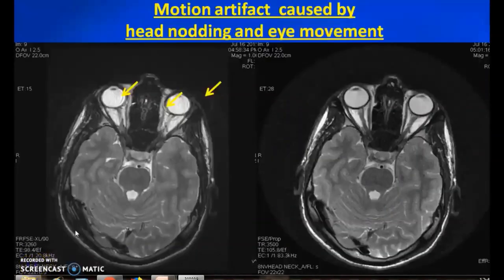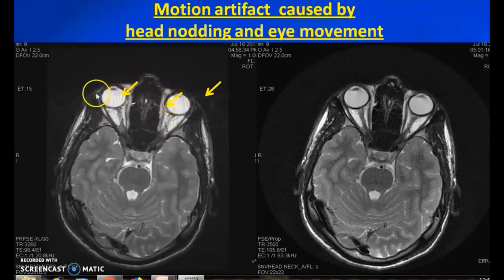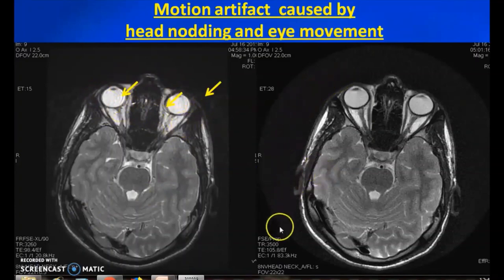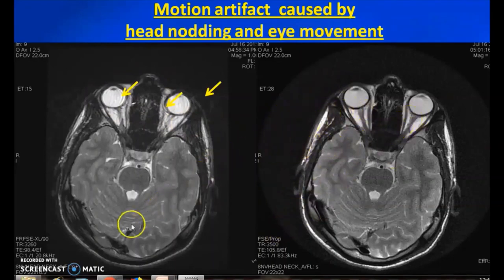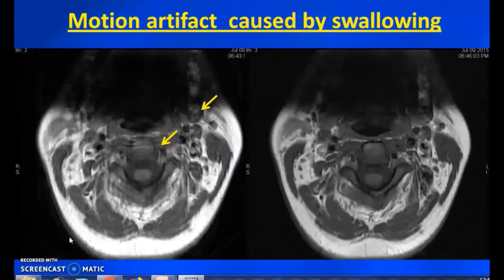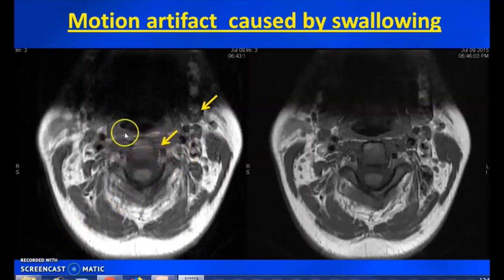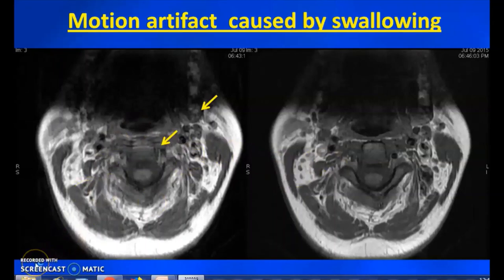Movement artifacts are always happening in the phase-encode direction. Head nodding and eye movements are some movement artifacts — this is particularly problematic in orbital studies giving a lot of image degradation. In such cases, you can use the movement correction sequence called PROPELLER or BLADE, which eliminates some amount of movement artifacts. Swallowing is also a kind of movement artifact seen in cervical spine or neck imaging. Just ask the patient not to swallow during the sequence.